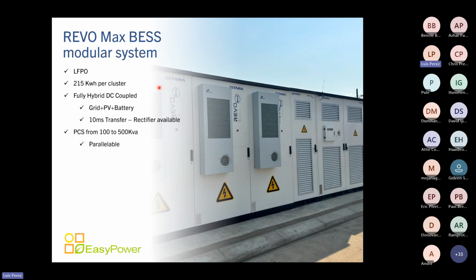PCSs range from 100 to 500 kVA, and they can be paralleled to scale up to larger systems. As I mentioned, our nominal battery system starts at 768 volts.